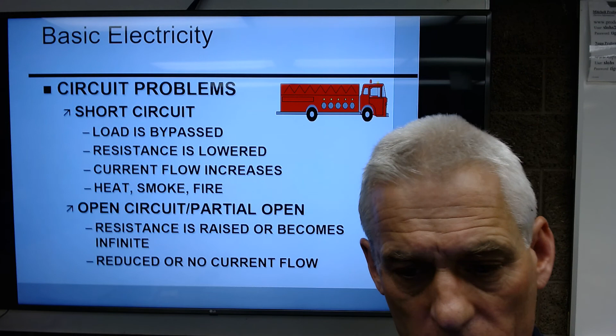So many people say to me, Mr. L, my such and such is not working, I must have a short. And I say, well, if it's not coming on, for sure you have an open circuit because no current's flowing. Now, it may be an open circuit because something malfunctioned, high current tried to flow, it burned a fuse or popped a circuit breaker, and now you have an open circuit. So you might have an open circuit because you burned it open, and that's being caused by a short circuit.